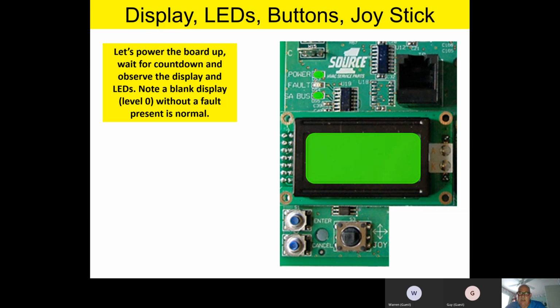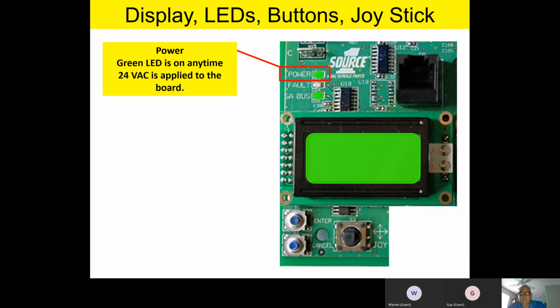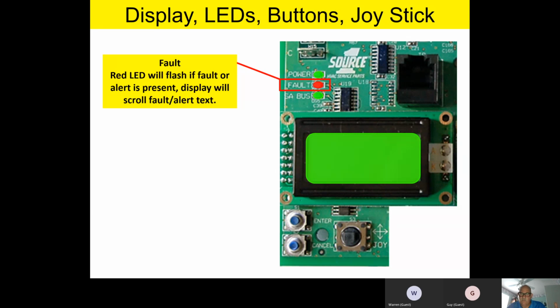Now we're going to refer to this idle or blank screen as level 0 or the home screen. You're also going to notice there's a power LED above it. If there's something on the SA bus, it'll be flashing as it communicates, on that little LED above where it says SA bus. Anytime you have power to the board, you'll have that green LED on. If you have a fault or an alert on the board, it'll flash that red LED, letting you know there's a fault or an alert.